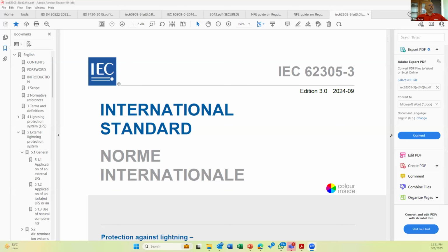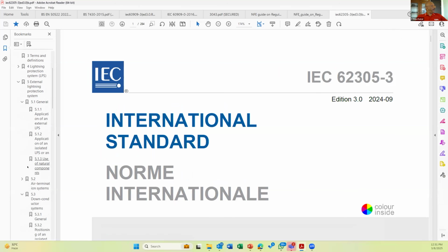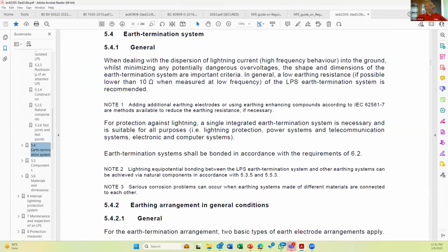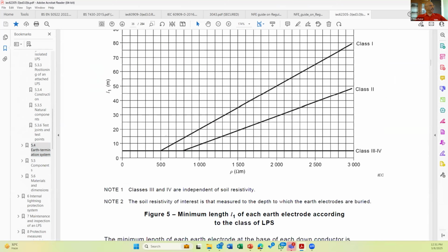Question from Mr. Mohit Kumar: is chemical earth pit allowed? Mr. Mohit, there is nothing called a chemical earth pit. These are some bogus things created and followed in the market. So don't go behind these bogus things. I will show you what is written and what has to be followed. The only standard which requests putting an earth enhancing compound, which we generally call chemical, is IS or IEC 62305, the lightning protection standard. Let me go to 5.4, earth termination system. 5.4 explains how the earth termination system has to be made.